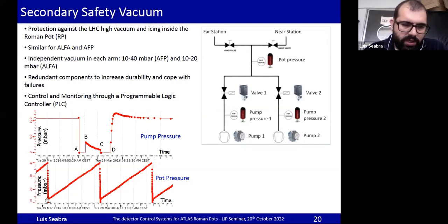So how does this work? I'm showing here several pumping cycles. On the bottom, you can see pressure increasing in the Roman pot, and when it reaches the limit of 40 millibar in the case of AFP, the pump starts working, so the pump pressure goes to 0, and then the valve opens, and it starts pumping the air between the stations. And then when we are happy with the pressure, the valve is closed, and then the pump stops working. And this is all done by using the PLC, the programmable logic controller.